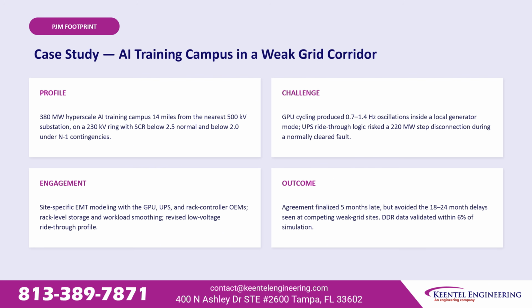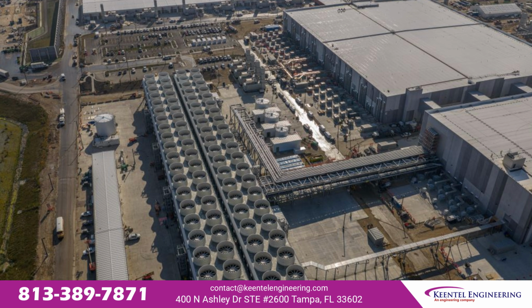We built site-specific electromagnetic transient models with the equipment vendors, added rack-level storage and workload smoothing, and revised the ride-through profile. The agreement finalized 5 months late, but avoided the 18 to 24-month delays competing weak grid sites saw, and the facility's measured data validated within 6% of simulation.